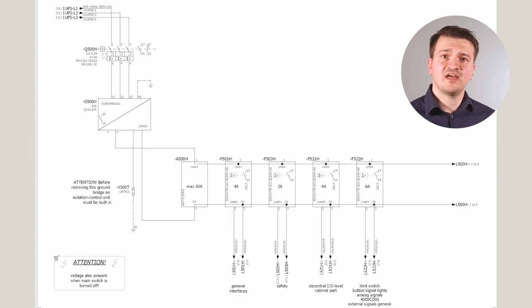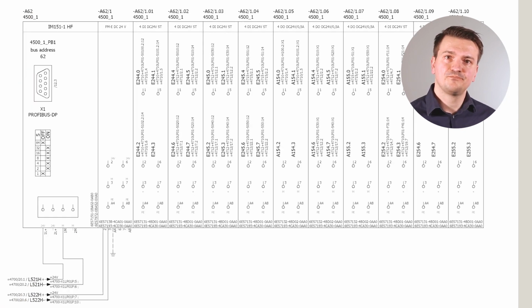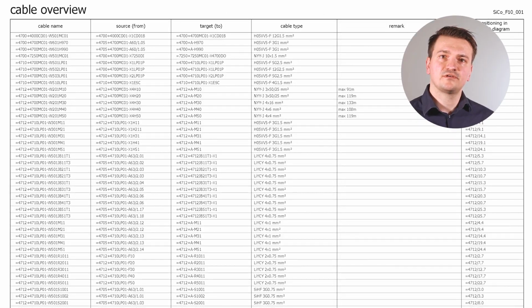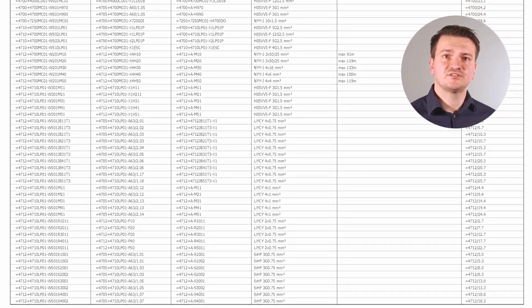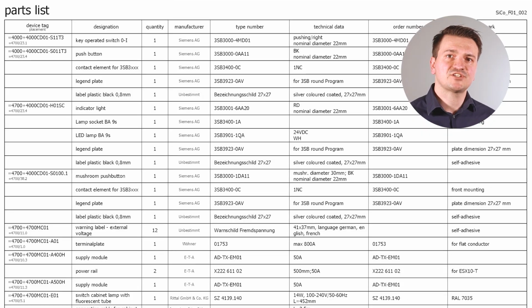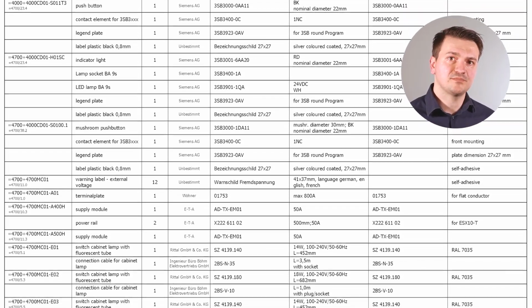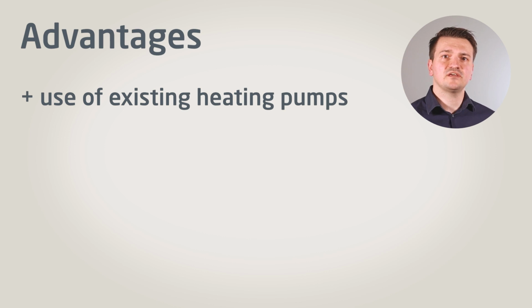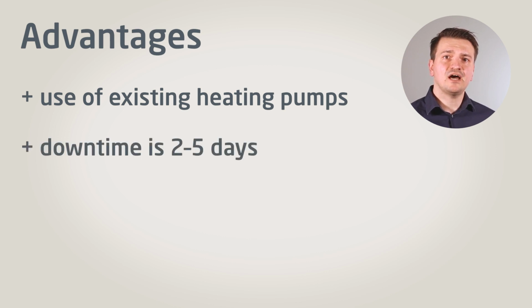New circuit diagrams and cable diagrams are also part of the scope of delivery. The interfaces to the PLC are configured by Siempelkamp, and the existing visualization will be adapted to the new functions of the frequency-controlled heating pumps. Once again summarized for you. The most important advantages of the frequency-controlled heating pumps are use of the existing heating pumps. The downtime for the installation is 2 to 5 days.